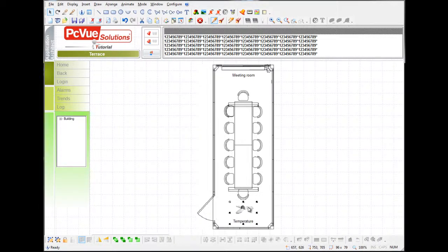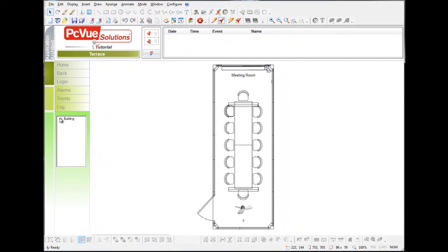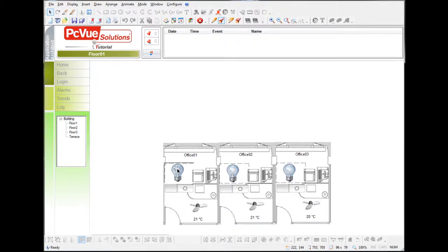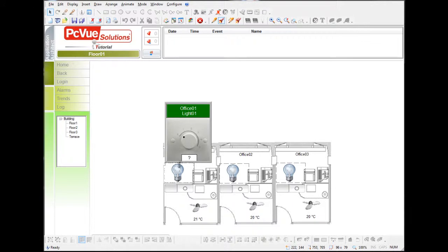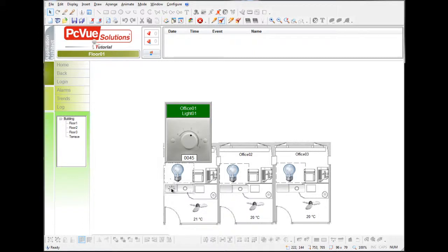Let's check floor one. The mimic has been updated. The open space and the meeting room have been removed. We can check that the popup for a light is now animated with the new variables created and that we control the light with the dimmer. Wait for a few seconds and an alarm appears on the light.